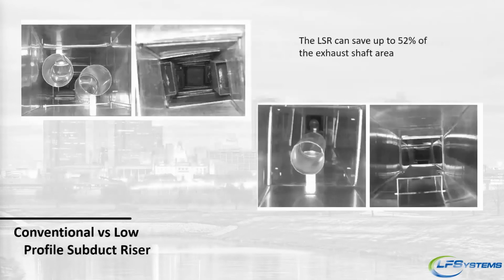And so a lot of installers will make their own. They'll basically take 4-inch or 6-inch pipe, cut a hole, fire caulk it, and then put a 90 and run a piece of 22-inch pipe. And it works. That works fine. The problem with it is it does take up a lot of space. When you're sizing up your shafts, you do have to take that out of your equation as free area because it's now taking up a lot of space.